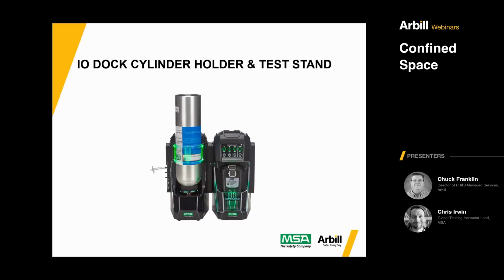One thing you might see is what's called a cylinder holder and test stand, or a docking station, where you can screw the bottle of gas in, and it can do auto testing for you. In fact, it can do a lot of different things, but I simplify what this does. Once it's powered on and everything looks green on the station, you can take this same small diffusion-based detector, but you can also get this for the larger pump-based device.